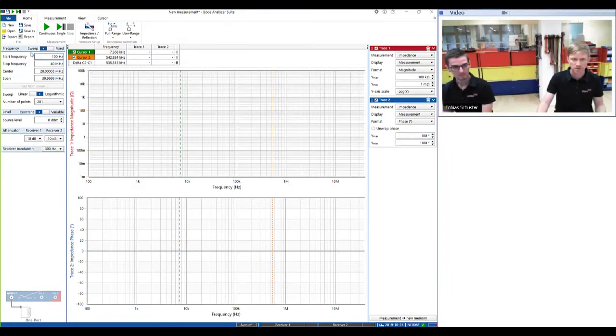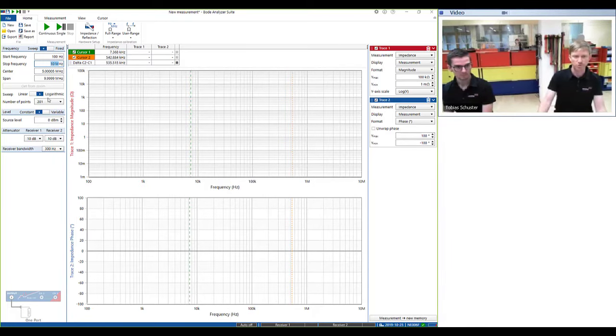And the first thing that I'm gonna do is to choose the frequency range of interest. So 100 Hz start frequency, I think that's a good choice, and we'll go up to 10 MHz stop frequency on a logarithmic scale, 200 points, that's sufficient. I'm going to use the full output level of 1 volt RMS of the Bode 100 and set the receiver bandwidth to 100 Hz because that gives us a pretty fast sweep with a good noise rejection.